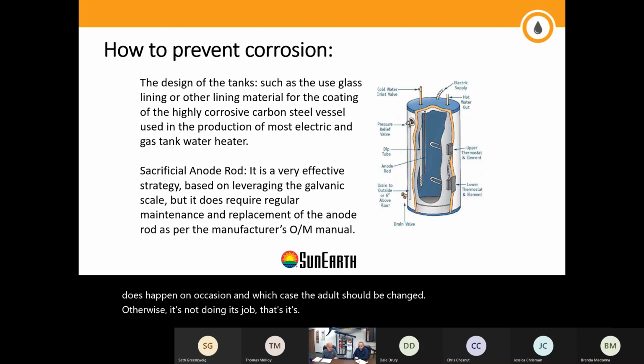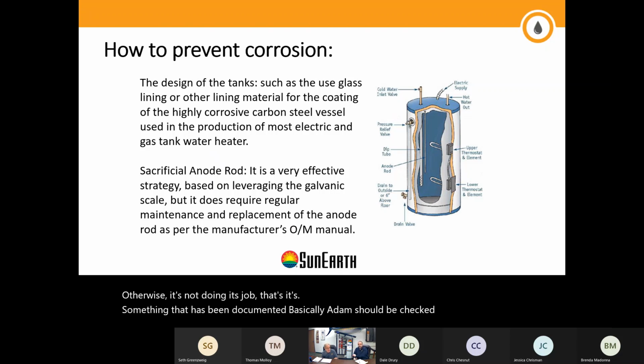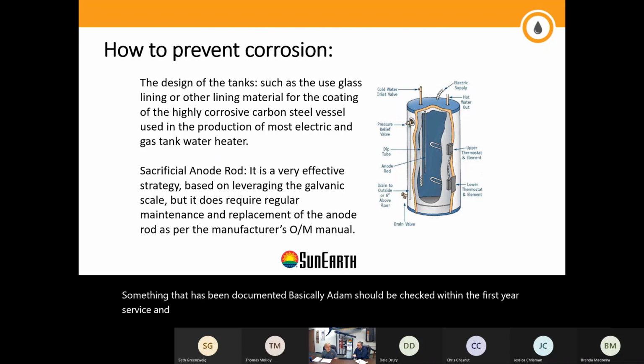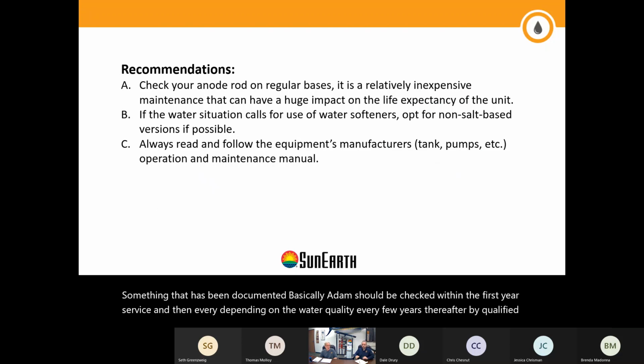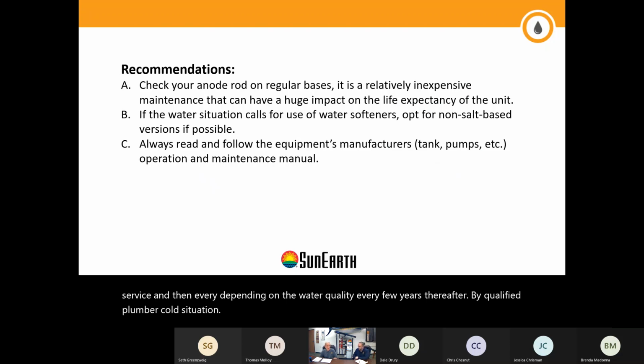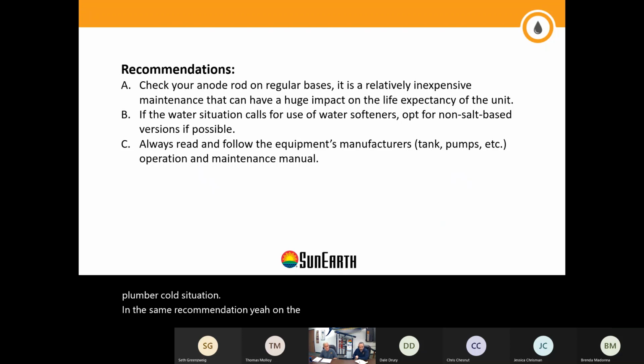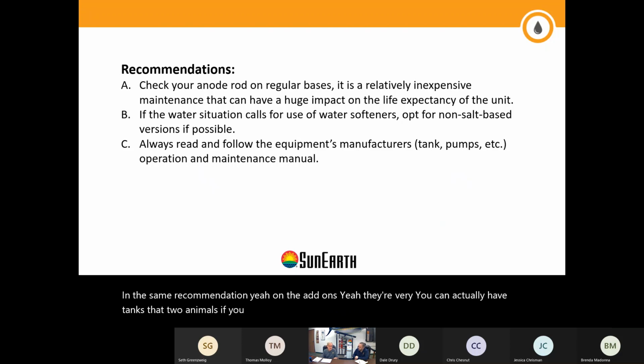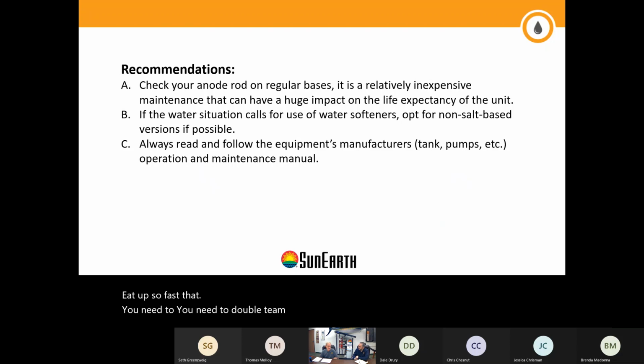It's something that has been documented. Basically, anodes should be checked within the first year of service, and then, depending on the water quality, every few years thereafter by a qualified technician. And the same recommendation applies. Yeah, on the anodes, you can actually have tanks that have two anodes if you're softening water to a point where it's going to eat up the anode so fast that you need to double team the softening part.